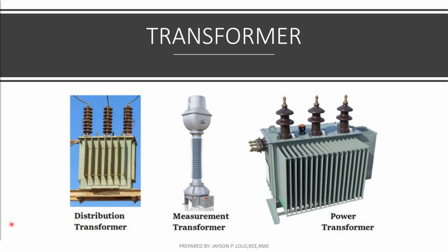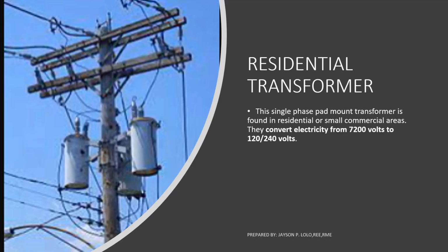Let's proceed with the residential transformer. This is the common one. This is a single phase pad mount transformer, which converts electricity, but primarily converts voltage from 7,200 volts or 13,200 volts to 120 or 240 volts. 240 volts is commonly used in the Philippines.